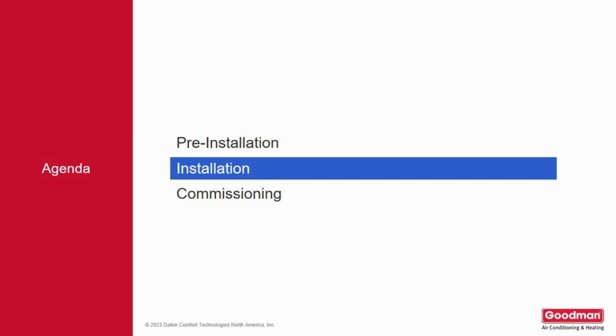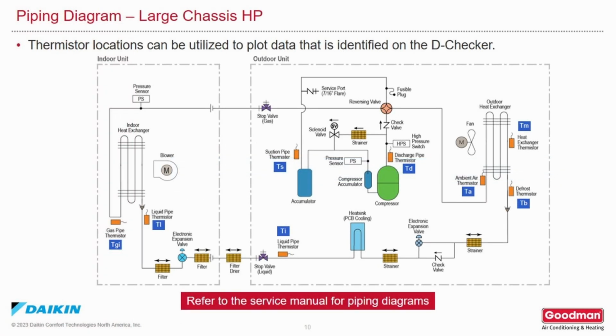Unit installation. Here's a piping diagram of a large chassis heat pump. Refer to the service manual for the diagram for the unit you're actually installing. These piping diagrams show the locations of the thermistors so you can plot the data and identify what thermistor you're looking at when you are using the D-checker. This makes starting up and servicing the unit much easier and more accurate than attaching your own thermistors to read temperatures.